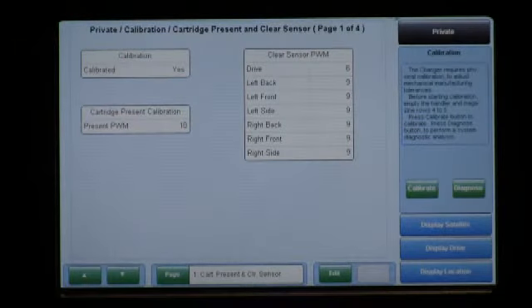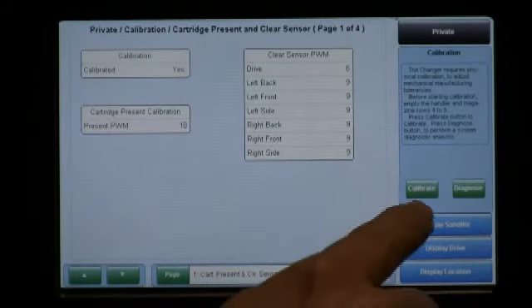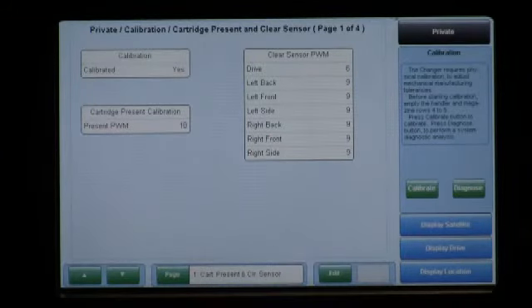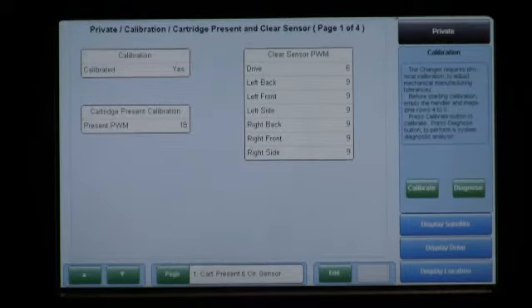So now that the private menu has been enabled and you're in the private calibration screen, you have a calibrate button option. At this point, you're at the stage where you will have to remove the magazines and remove the tapes from the specific rows that need to be emptied.